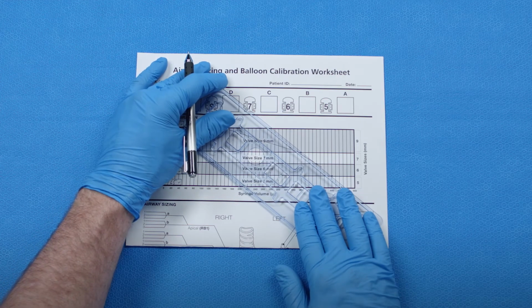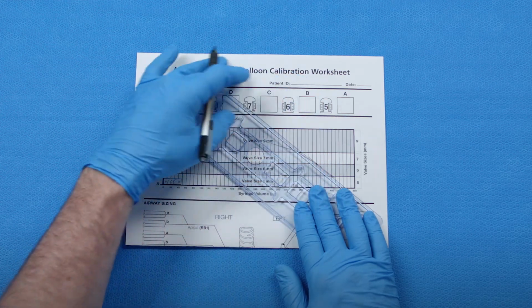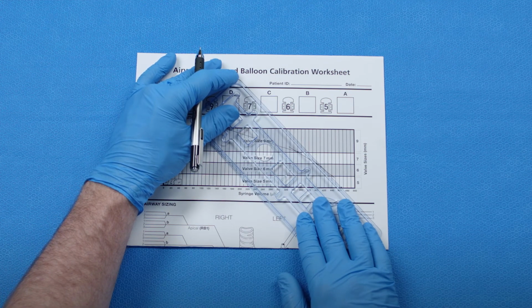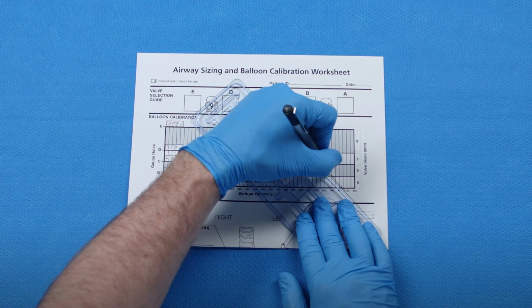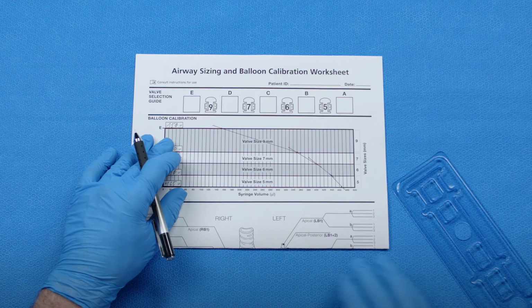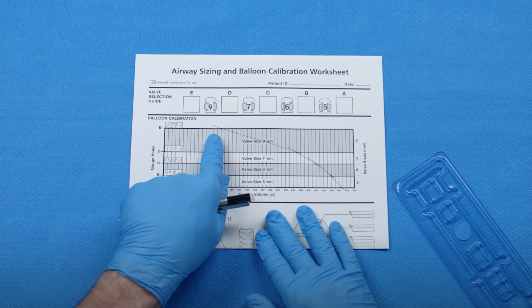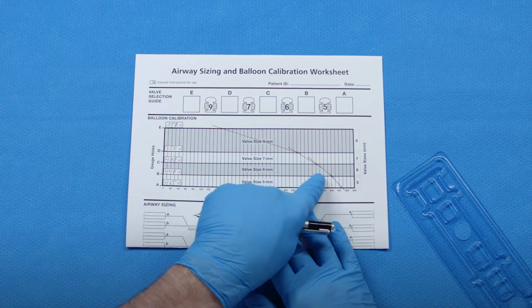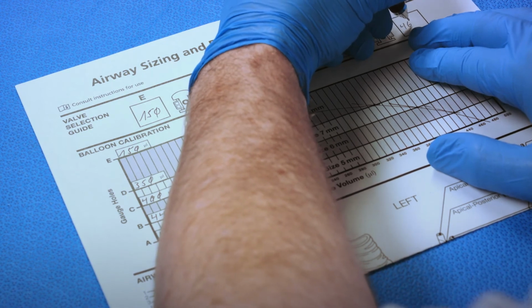After all the gauge hole sizes have been recorded, plot the values and connect each of the points on the balloon calibration section of the worksheet with a straight line. Verify that the curve is continuous, then transfer the numbers to the valve selection guide portion of the worksheet.